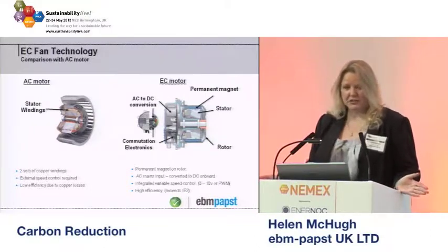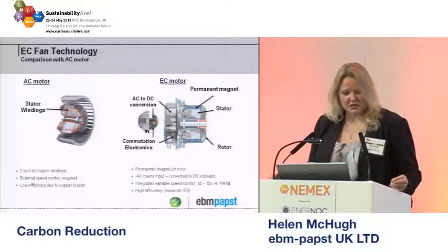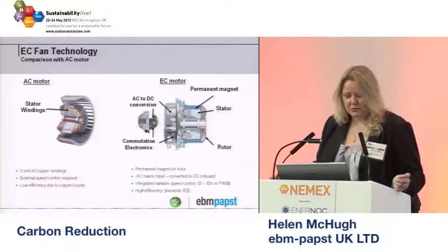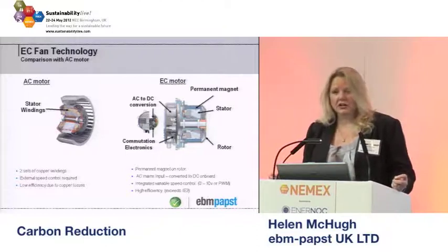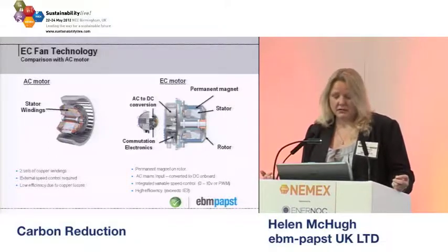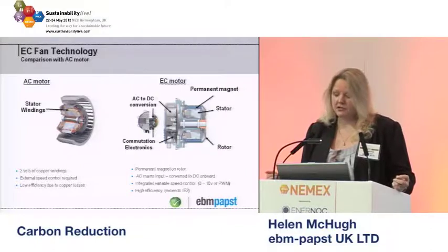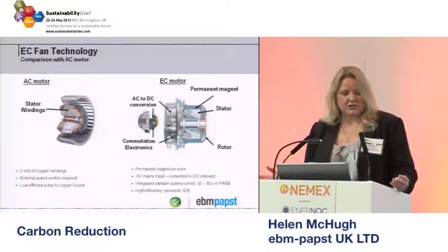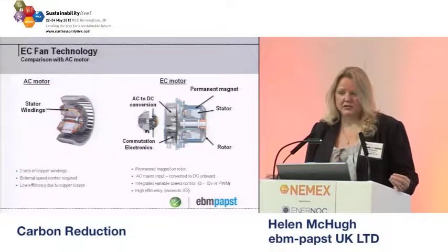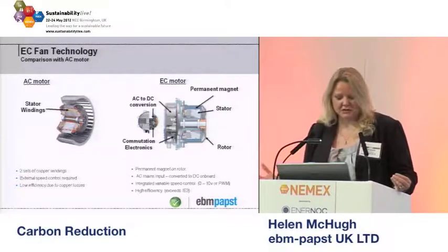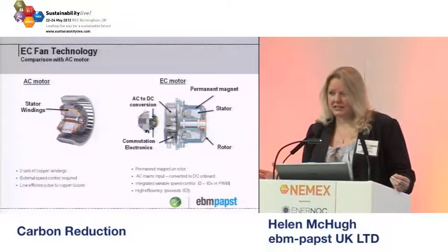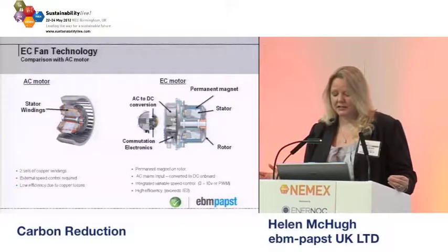I don't want to spend too much time on the technology—you can come and see us later if you want to learn more. But just to give a brief idea of energy-efficient motors: on the left you see a cut-through of an AC motor, our typical external rotor motor. These are often quite inefficient because of losses within the motor—there are two copper windings, and you have to induce a secondary magnetic field to get rotation. Basically, the efficient motors we're talking about are high-voltage DC motors, which contain a permanent magnet, replacing some of the copper windings.